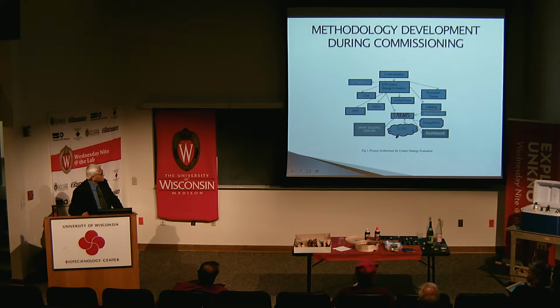Now what happens here is, every day of the cooling season, you test the control strategies, which the operator can schedule so that they come on automatic. And the data collected during the on-peak period, say 8 a.m. to 5 p.m., is sent to the cloud. Because during the on-peak period, when you are testing the control strategies, it's not possible to evaluate the data. So during the off-peak period, when there is no occupancy, then you evaluate the data and come up with the information you need. And at this point, the relevant information is sent to the dashboard where the operator can take a look.